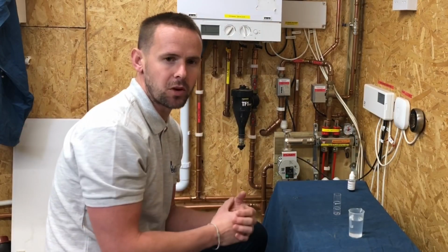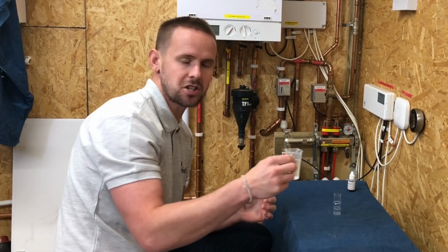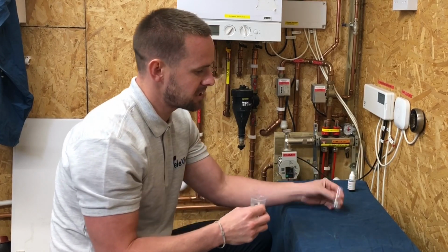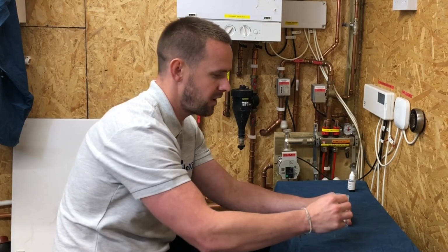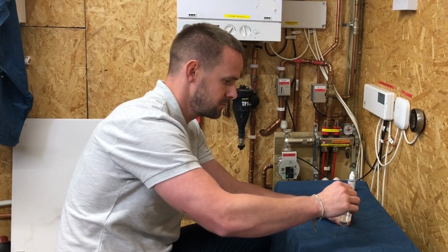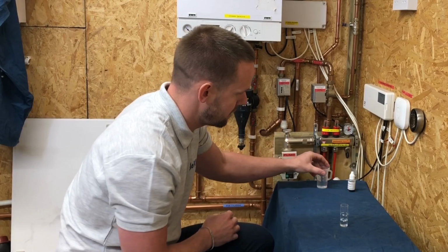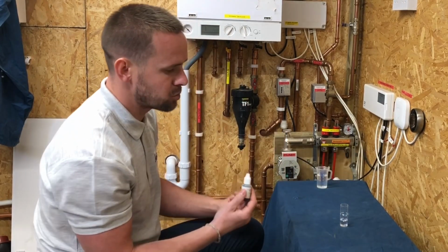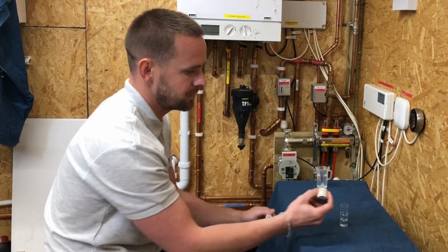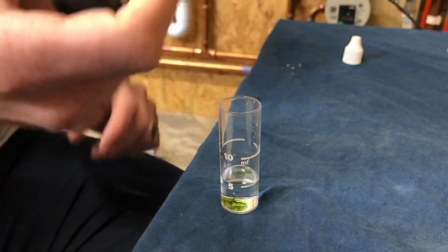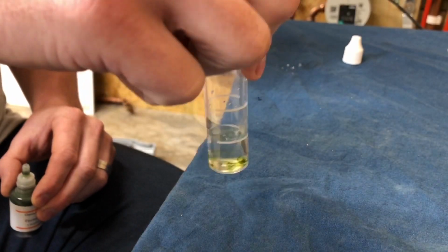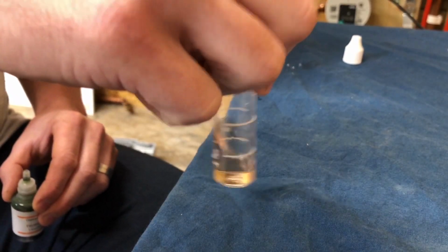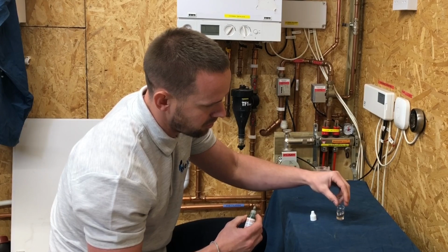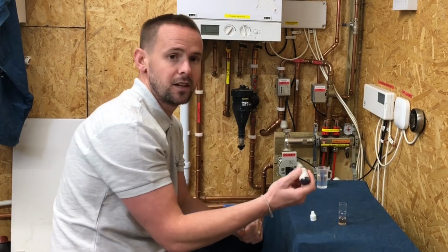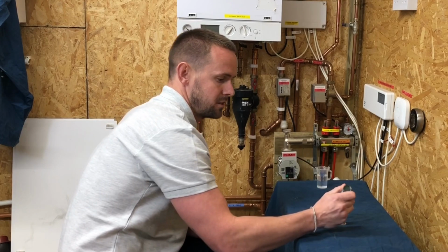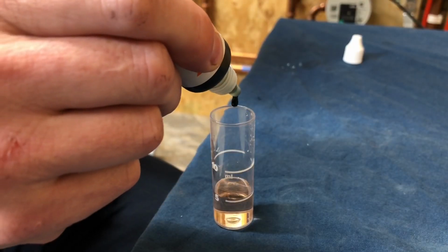So now we're going to do the total hardness. So once again, I've changed the water, so no contaminants. So we're going to take the little test beaker and fill with 5 ml. So we're just going up to the line. So we've got some reaction agent here. So it's a very simple drop test. The first drop starts the process. I'm just going to give it a little shake in between. So what we want is it to turn green. So each drop from now on counts for 1 degree hardness. So it's 1.